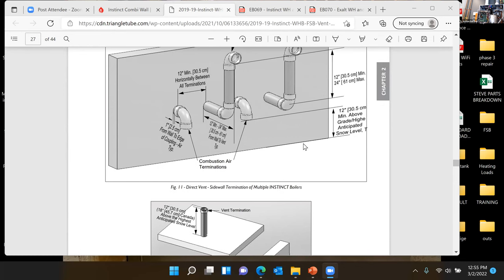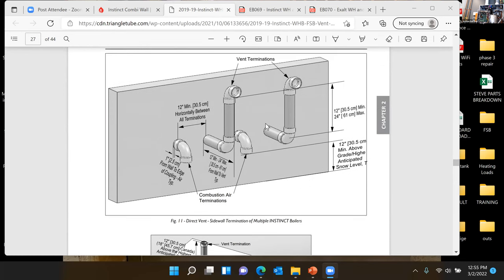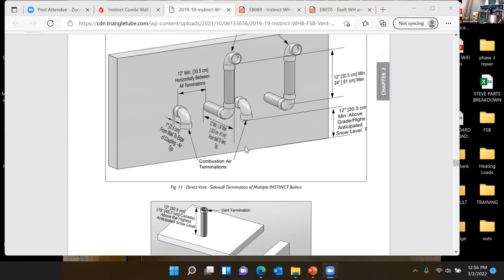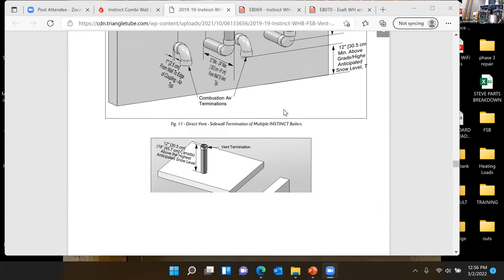On the cascading, pretty much the same thing. If we're doing multiple boilers, having that separation, again, the 90s down. The chimney kits that Centrotherm and DuraVent have are great. Those are 100% approved for installs. So if you're going to bring your exhaust up through a chimney, you totally can do that. No issues there.